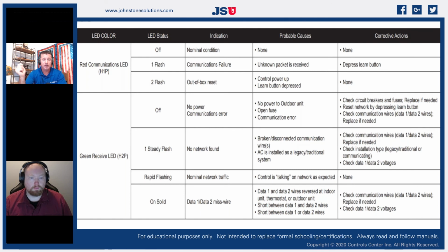Typically on our communicating equipment, we have a red communicating LED light and a green communicating LED light. And when we look at those, they'll give us an idea of what's going on. So if I've got a single flash on the red light on startup, I've got some kind of communication failure. If I look over at my green light, a single steady flash on that green light tells me that there's no network found and that I potentially have a broken or disconnected communication. So I have a control wire that is not passing voltage through it properly.